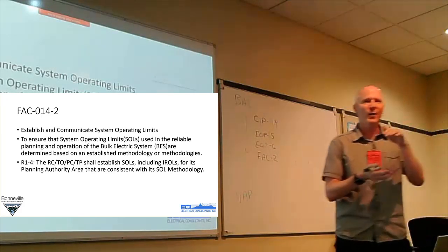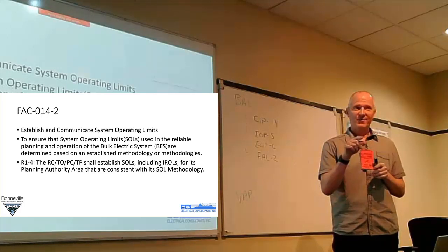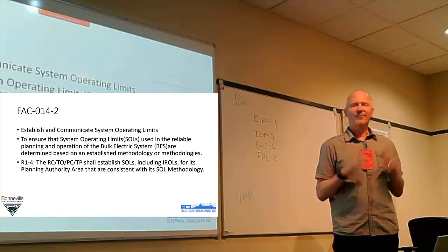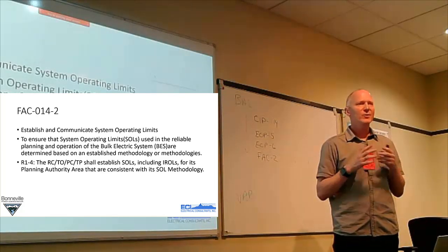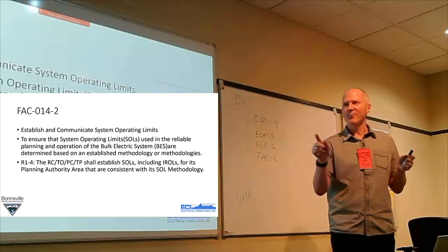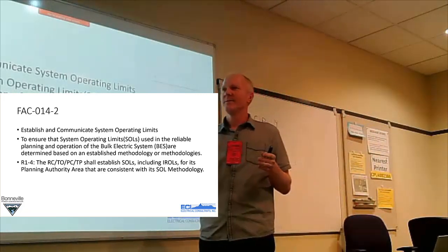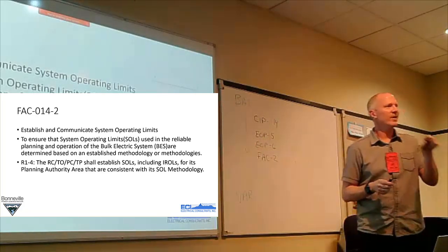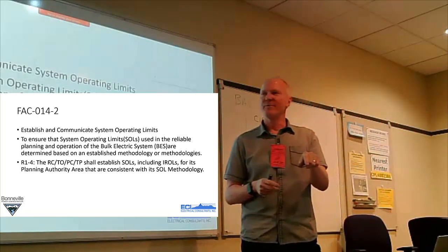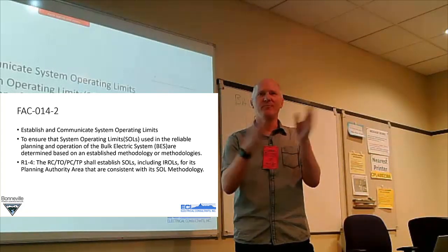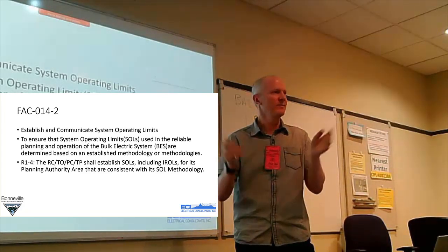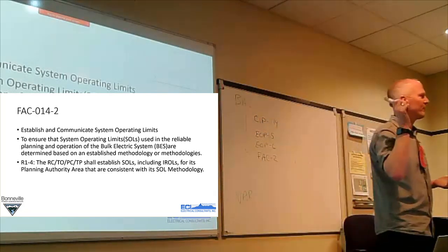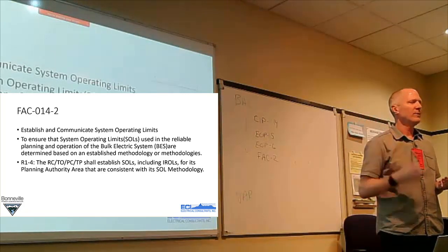One of them is in the power flow, and PowerWorld is totally lined up for this because you can click on these things. If something violates, you open it and run it again, and if something else violates, you open that, and you get 4 of those, and then it's an IROL. So in thermal stability, you can open up 4 things, and if you have to open up a 5th, that's their determining factor in the thermal world, that's an IROL, whether they're close or far. But again, it's methodology. So there's a lot to learn in looking at the different interconnects' IROL methodologies.